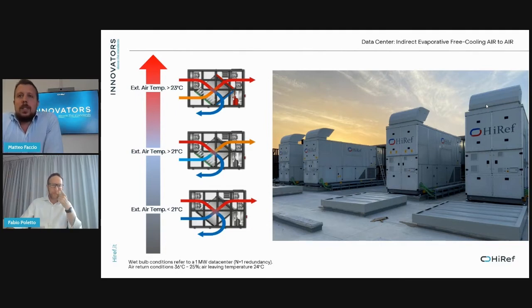When the external air temperature increases and exceeds 21 Celsius, we can activate an adiabatic system that sprays water in the external airflow stream. We can extend the free cooling thanks to the evaporative effect, and then we can move from dry free cooling to wet free cooling. This works until the wet bulb temperature, in this case, reaches around 23 Celsius. Only in this period, the compressor starts providing the top-up mechanical cooling. Of course, it's up to the customer to decide to size the compressor for the nominal cooling capacity, in order to have a fully redundant system inside the same unit.